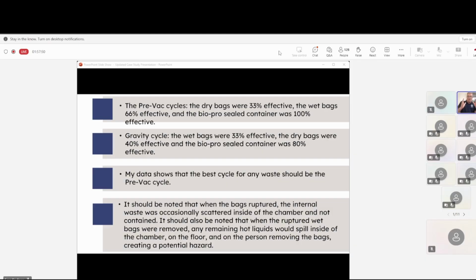And of course, the more you put bags together, the less you're insulating each other. And that effectiveness is actually going to start going down. And you know, you can increase the times to help do it, but even at an hour, it may not be enough. The gravity cycle, the wet bags were 33% effective. That's 3 in 10 with 5% trash in it. The dry bags were 40% effective. The BioPro 300 was 80%. It failed on the dense hard pack.